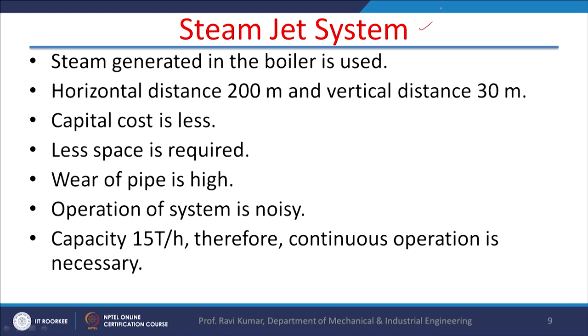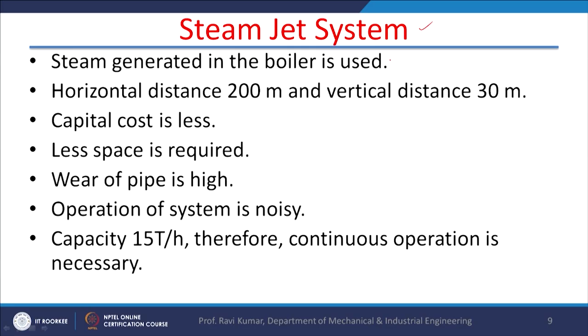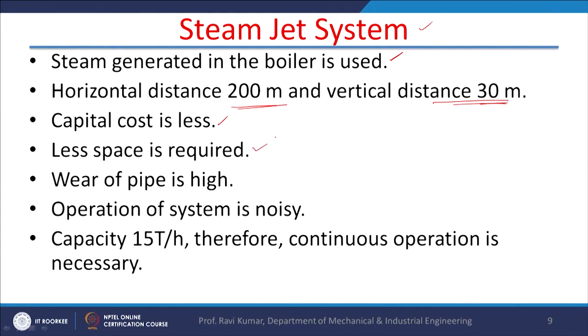The last system is the steam jet system. In it, steam has to be produced — usually a separate steam generation system is used, kept at a horizontal distance of around 200 meters and a vertical distance of about 30 meters. Because steam has very high enthalpy, less steam is required, so capital cost is less and less space is required. However, wearing of the pipe is also high, as in the case of pneumatic systems.